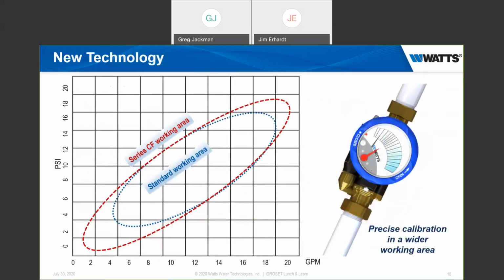Another big aspect of the iDROSET, it has a very wide working window. What you'll see on the spec sheet, which I'll show you where you find those, is that it has a very wide range of flow rate. So you have a much wider working area as compared to a traditional circuit setter. The technology inside the valve allows it to work under this larger window than is normally associated with either a fixed orifice or variable orifice balancing valve.